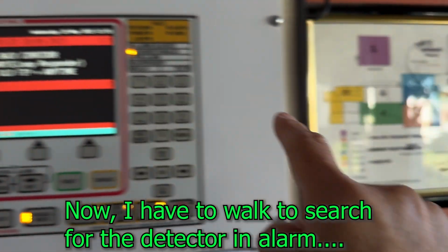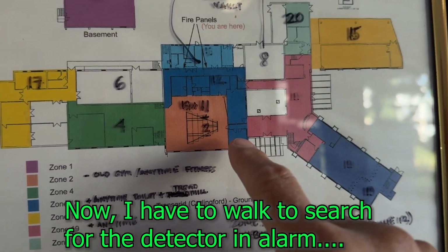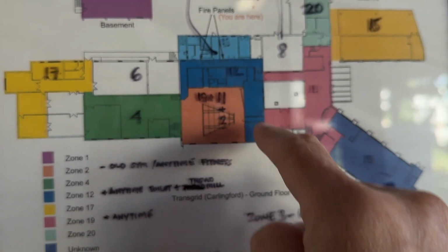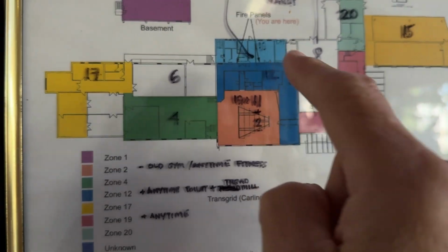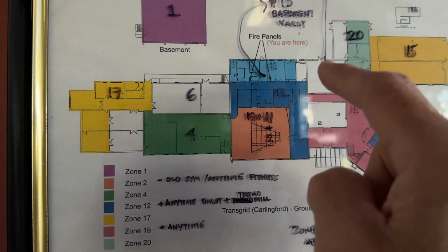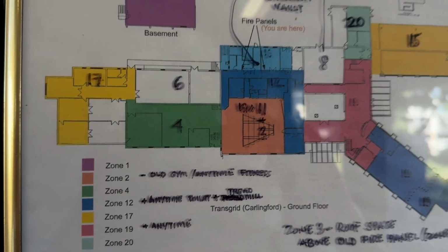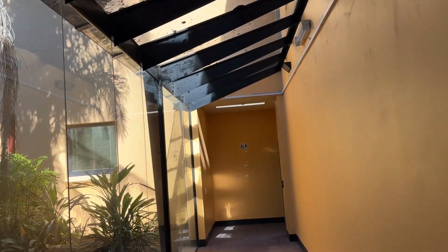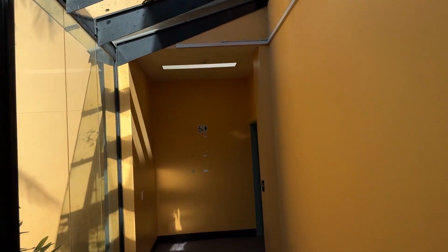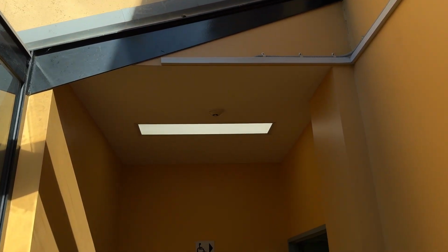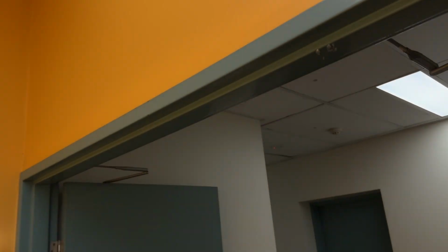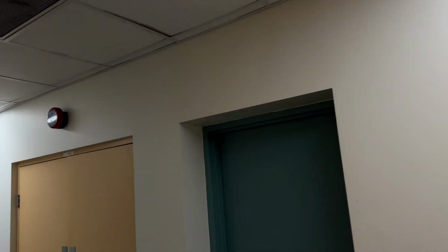What you're going to do next is go into the field and look around. Zone number 12 is Anytime Fitness plus the back corridor. We're going to look around for any detector with a red steady light. While walking around, all you have to do is look on the ceiling, on every detector. This is the back of the Anytime Fitness.